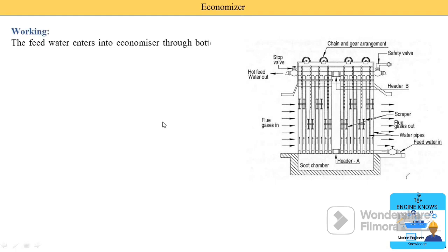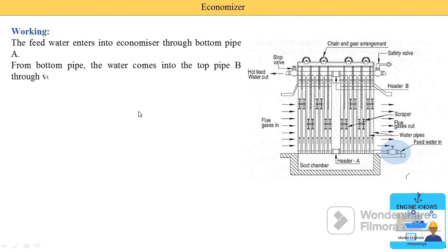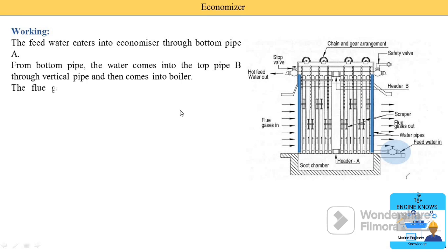The feed water enters into the economizer through the bottom pipe A — the feed water inlet pipe. The water then comes into the top pipe B through the vertical pipes, and then goes into the boiler. Water enters at the bottom, moves up through the vertical pipes, and comes into the horizontal pipe B, after which it is supplied to the boiler.